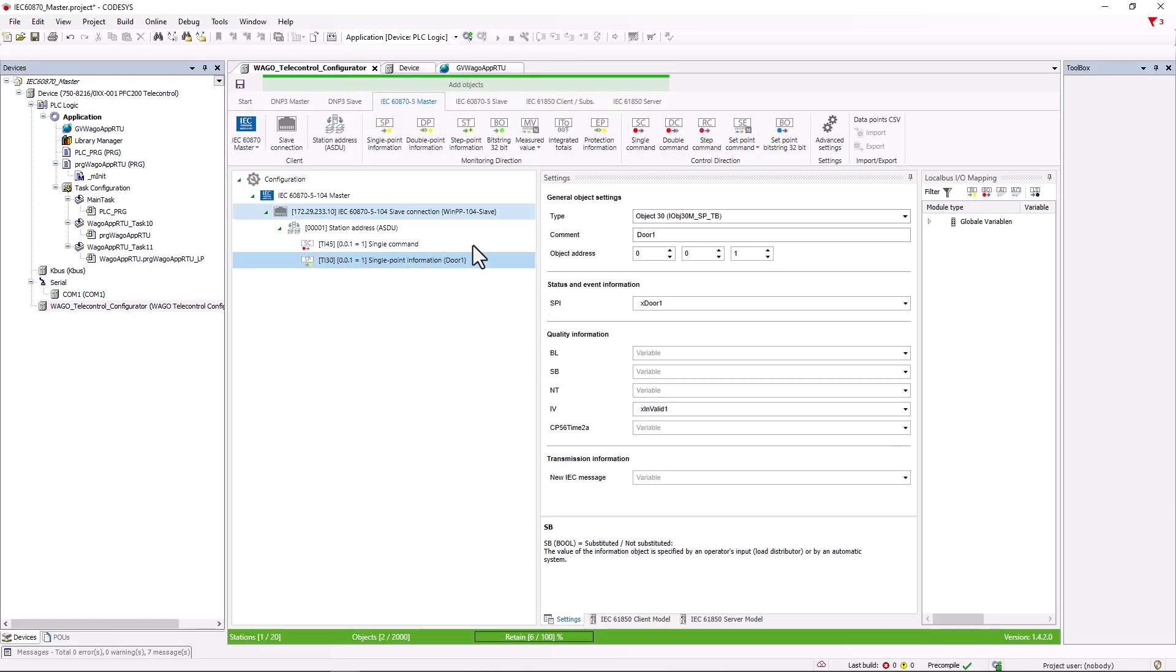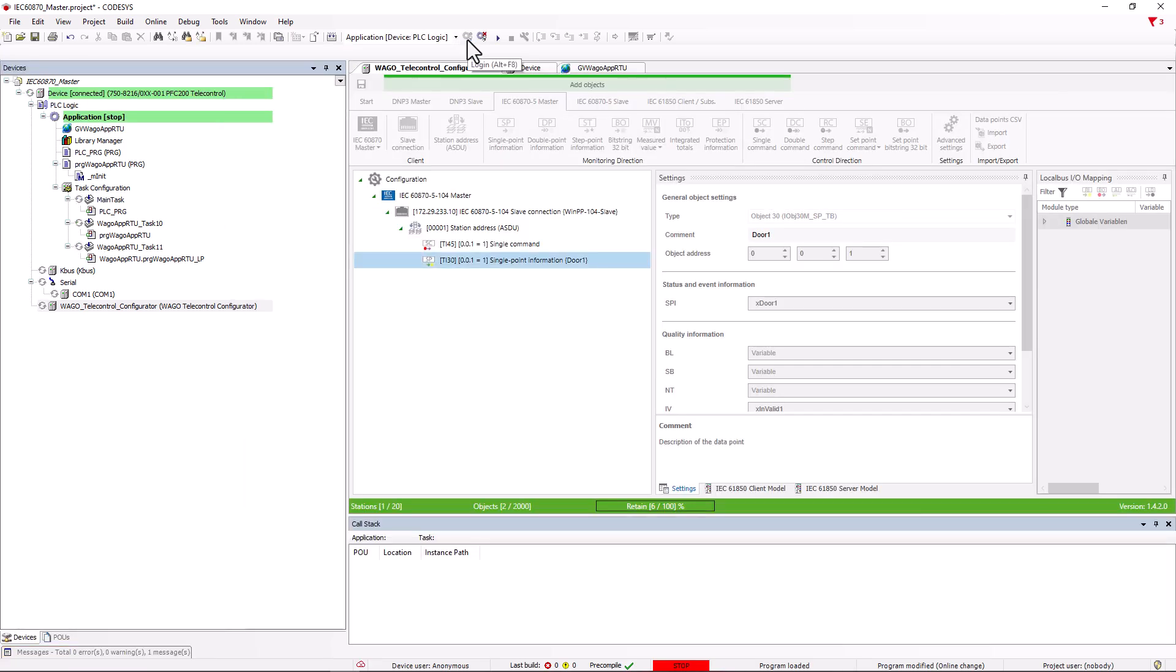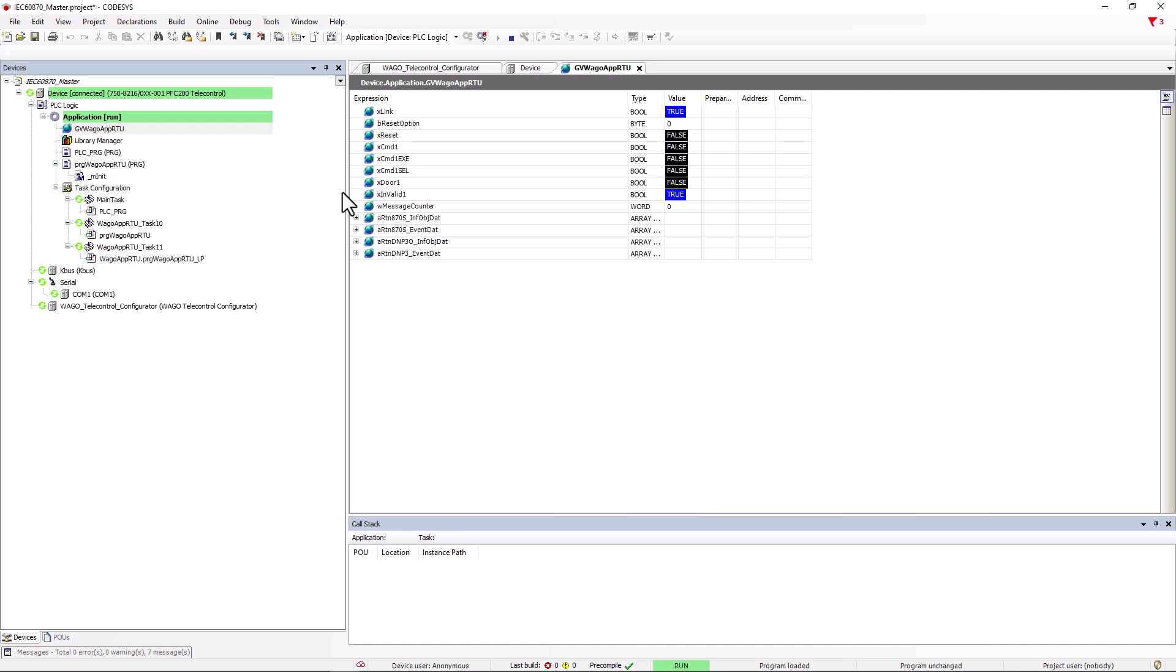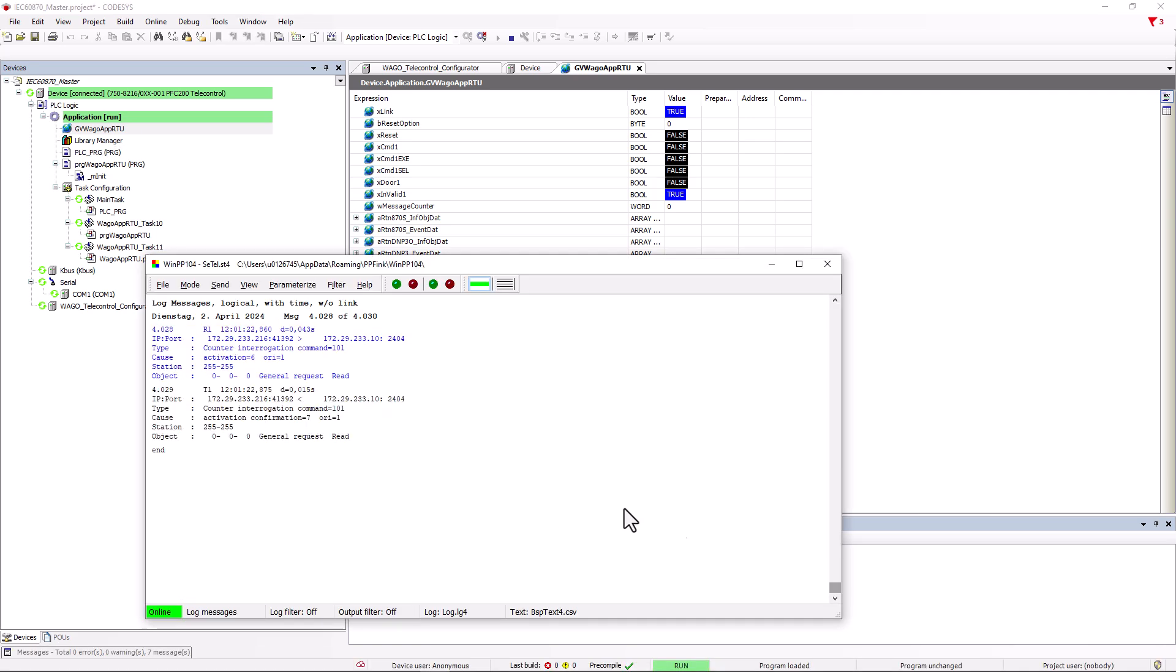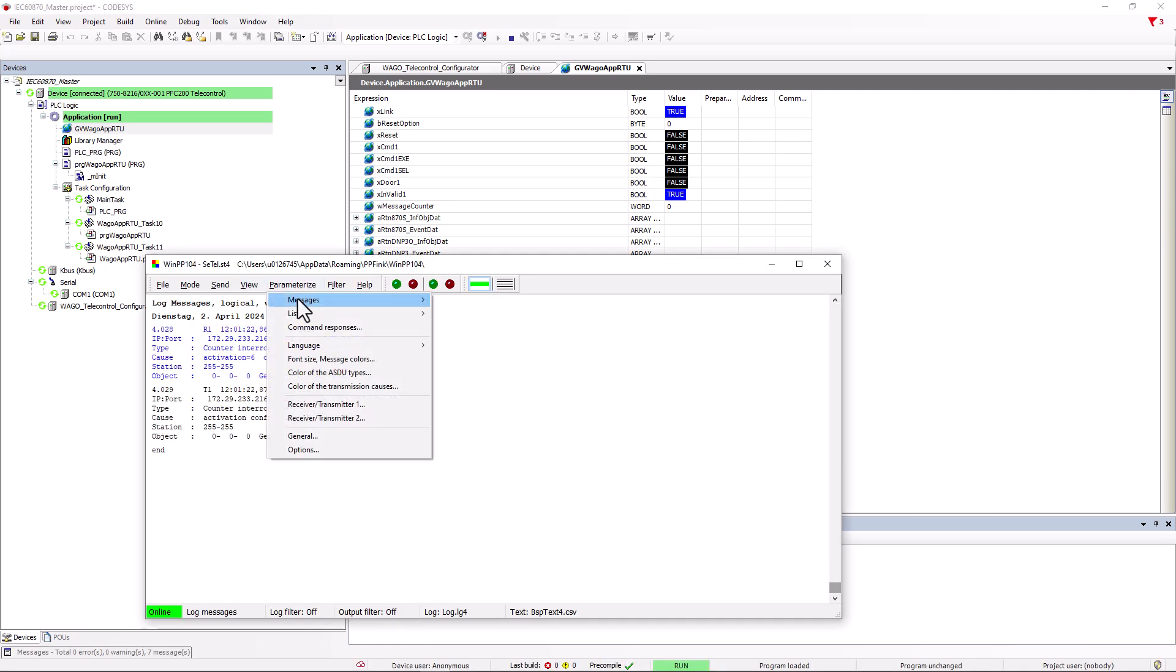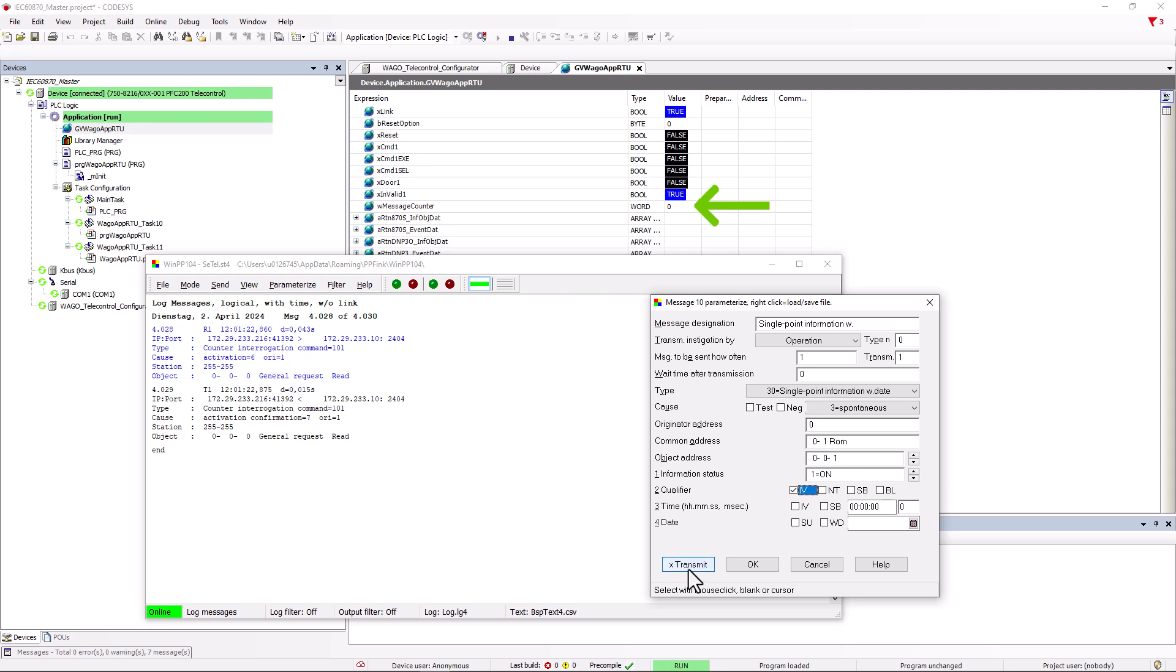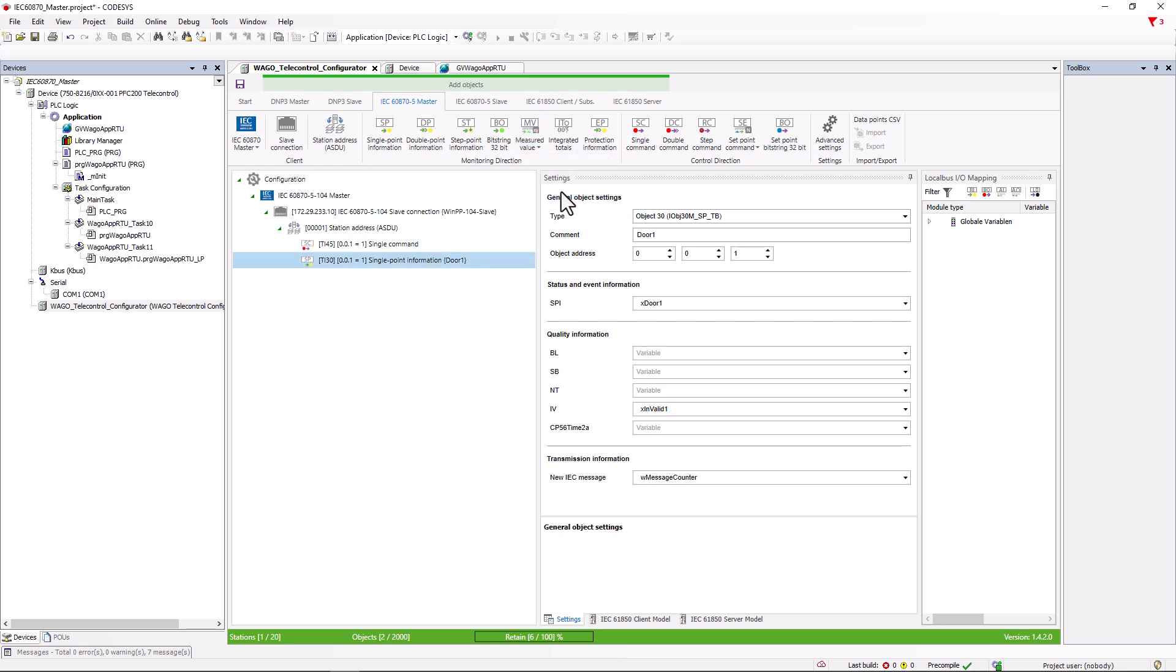If we now send DoorContact1 again, the variable for the IV bit will also be set. In the bottom area, Transmission Information, we can create a word variable in which the number of messages received is counted in order to use this value in the application or to create analysis with it. If we now use WinPP to send the door contact message a few times, we can see how the value increases. Similarly, we can create a measured value and assign it to a real or integer variable, depending on whether the measured value is a scaled, normalized or a floating point number.